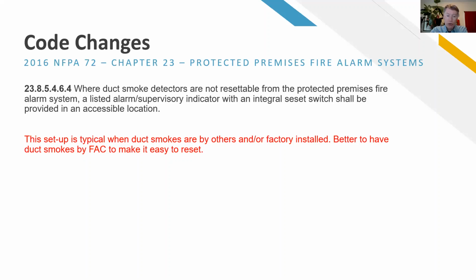Yeah, and for all of those listening that do have factory installed duct detectors that are not tied to your fire alarm system, there's some aspects of the code that allow that. That's always something you might want to put on a capital request at some point. I won't go into the reasons, but it's always good to have, in my opinion, duct smoke detection tied to the fire alarm system as opposed to standing alone. They often end up abandoned and people just don't look at them, and they're hard to get to.